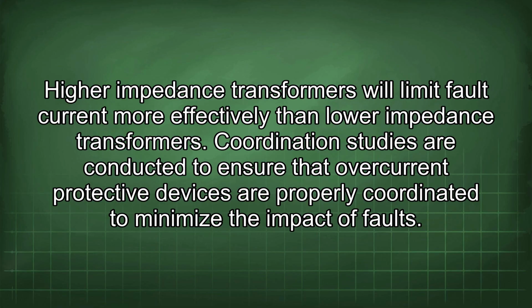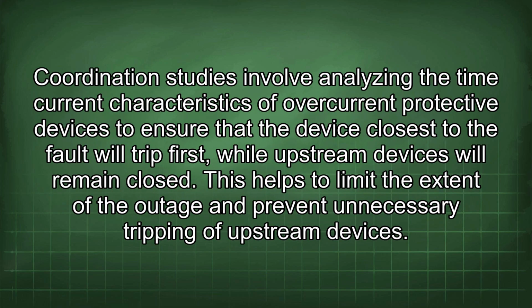Coordination studies are conducted to ensure that overcurrent protective devices are properly coordinated to minimize the impact of faults. Coordination studies involve analyzing the time current characteristics of overcurrent protective devices to ensure that the device closest to the fault will trip first, while upstream devices will remain closed. This helps to limit the extent of the outage and prevent unnecessary tripping of upstream devices.